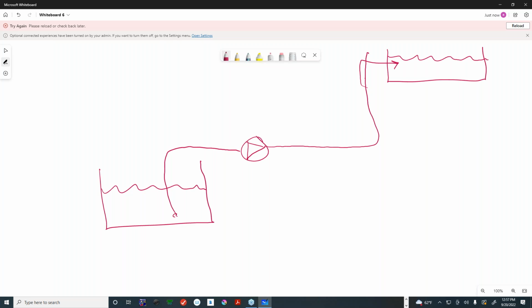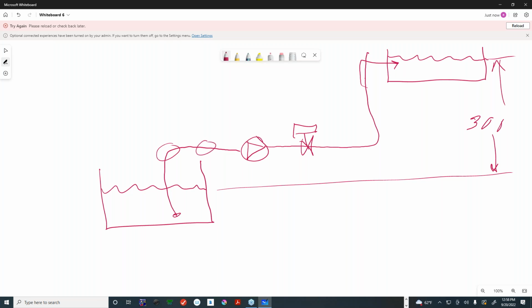So we had to calculate the water level difference for the static head. So that was the distance from here to here. And we had to calculate the pressure drop, which is, again, the pipe. Let's assume there's an elbow there, there's pipe there, and there was a control valve over here. And we had to do all of that calculation plus the water level. In our case, I think it was like 30 feet, something like that, for the height of the different tanks. So yeah, that's how it's done.